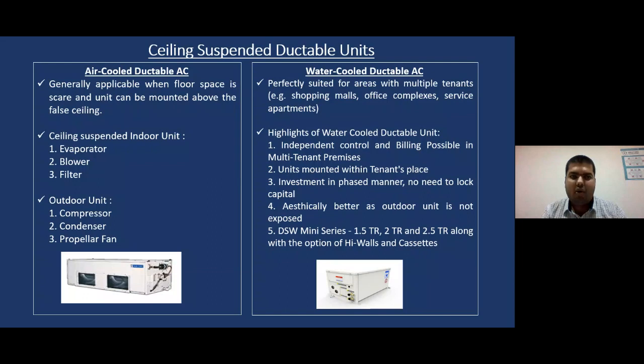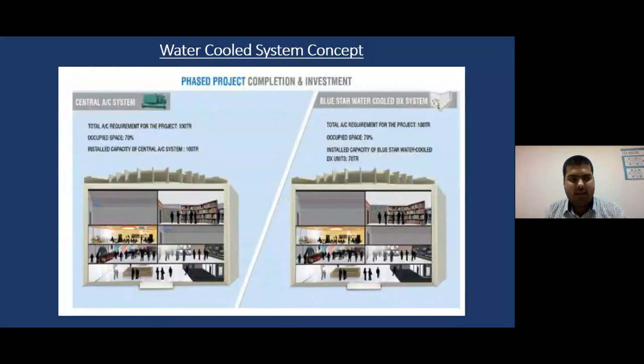So what is basically the water-cooled system concept? Here's a basic comparison between a chiller system and a water-cooled DX system. Suppose the total requirement as per area is 100 tons, but the occupancy is only 70% at that time. The builder can cater for only 70% at that time, and if required, he can add more later in a water-cooled DX system. But in case of a chiller system, he has to buy the complete unit of 100 tons in the first go, and he has to pay that initial cost at the very beginning of starting a mall. In malls, the occupied space is very small initially and then it increases. At that period, a water-cooled DX system is very much required.